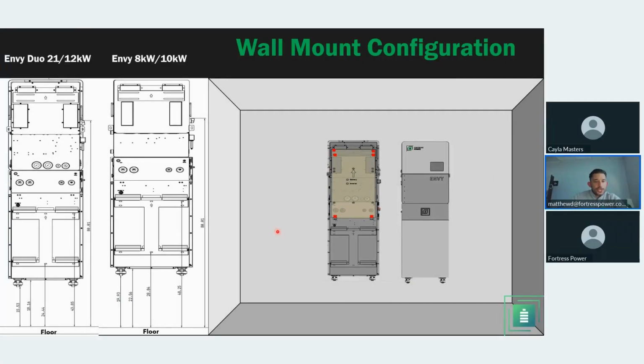Wall mounted configurations. This is basically a guide to let you know how high you can install your system before you violate NEC code, essentially, right? NEC code doesn't allow for the disconnect or the highest disconnect at the highest position to be above 6.7 feet. And so basically this is a guide to let you know how high you can put it before you go to that limit, right? And this is for both 21, Envy Duo 21, Envy Duo 12K, Envy 8K, and 10K, right?